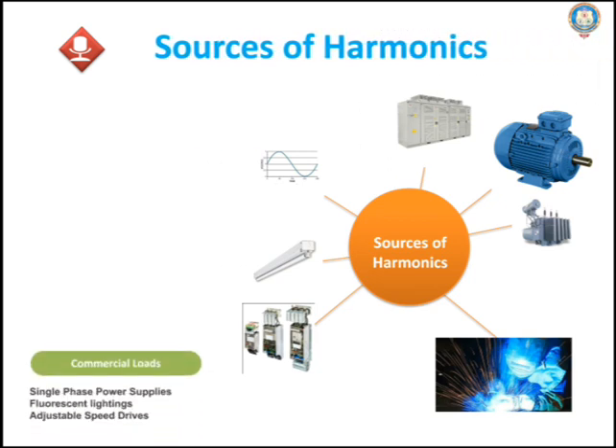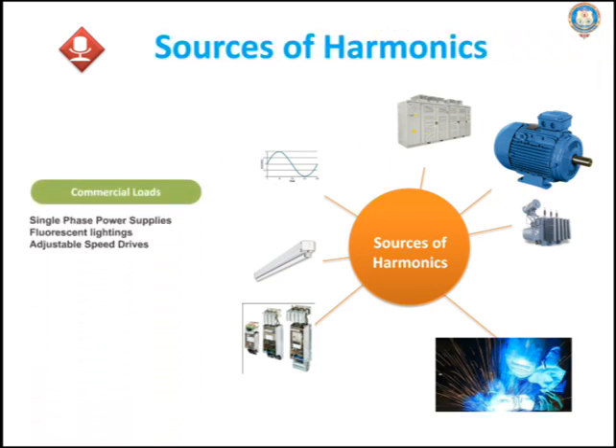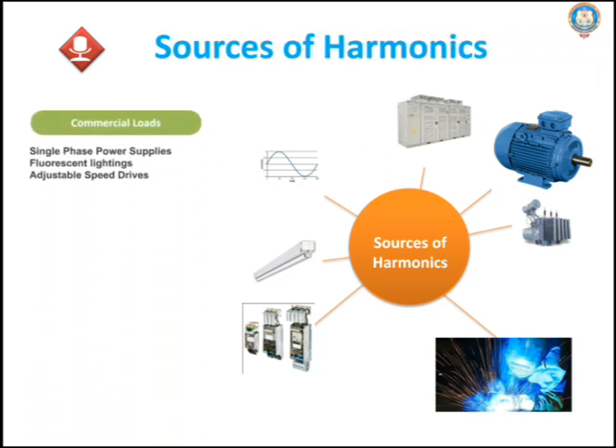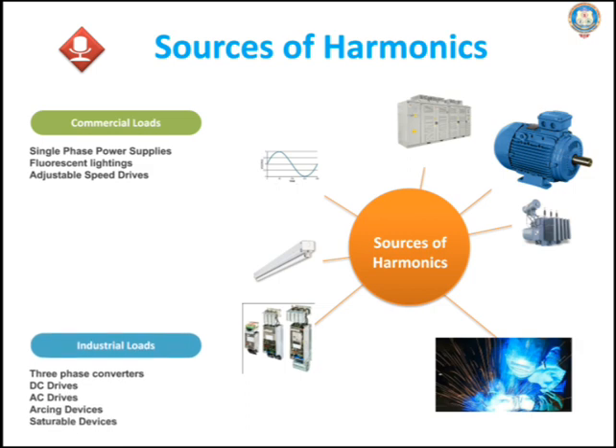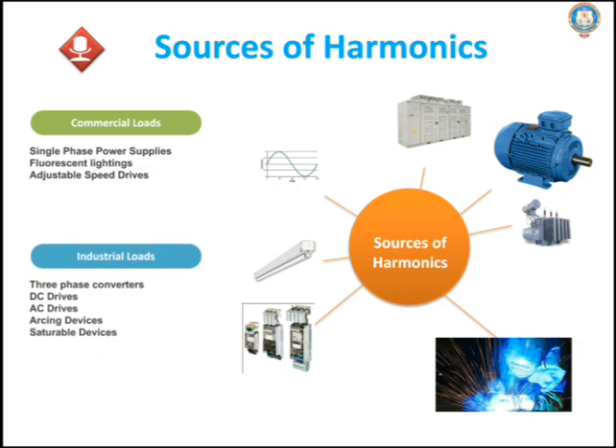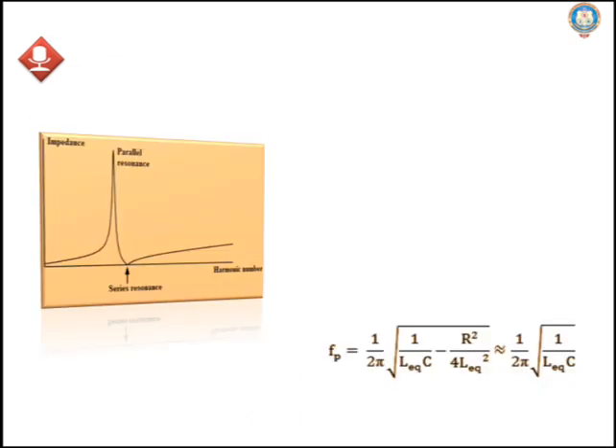What are the sources of harmonics? The sources of harmonics are commercial loads and industrial loads. Commercial loads include single-phase power supplies, fluorescent lightings, and adjustable speed drives. Industrial loads include three-phase converters, DC and AC drives, arcing devices, and saturable devices.